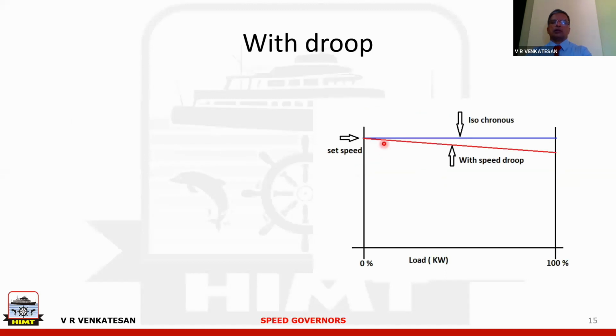So in the case of this alternator, this is what is going to happen. As the load keeps on increasing, speed will keep coming down. So if the engine is running at this much kilowatt, the speed will be here. How will you restore the speed to 60 hertz? Then you have to again turn the motor on the governor, which is a speed setting knob we have in the control room. So by adjusting that, this entire line can be brought up like this. So this point will move to here, and the frequency will be again 60. If you don't make that adjustment, it will remain here.